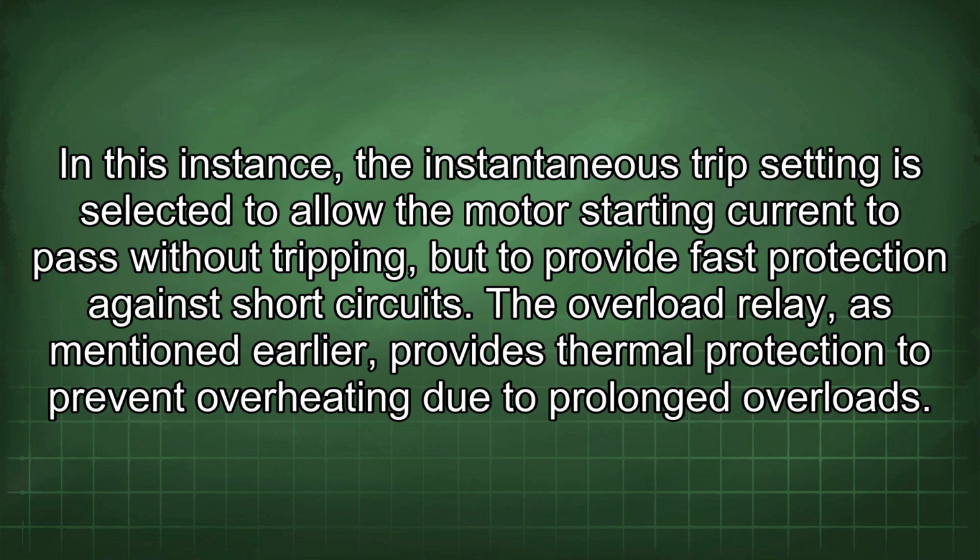In this instance, the instantaneous trip setting is selected to allow the motor starting current to pass without tripping, but to provide fast protection against short circuits. The overload relay, as mentioned earlier, provides thermal protection to prevent overheating due to prolonged overloads.